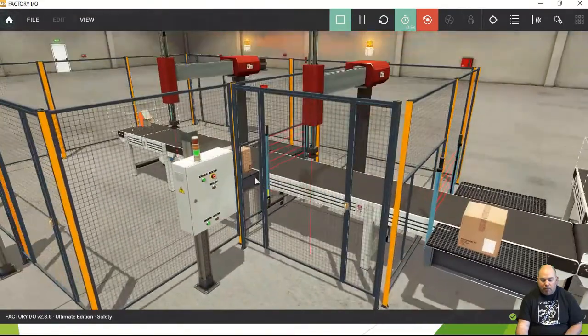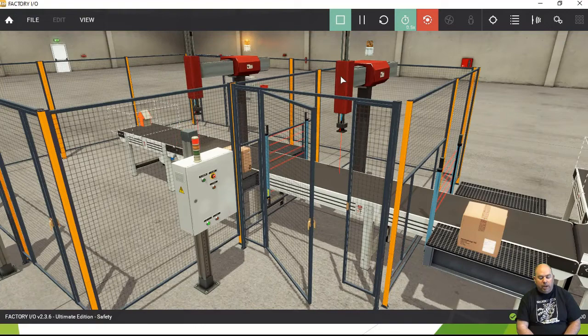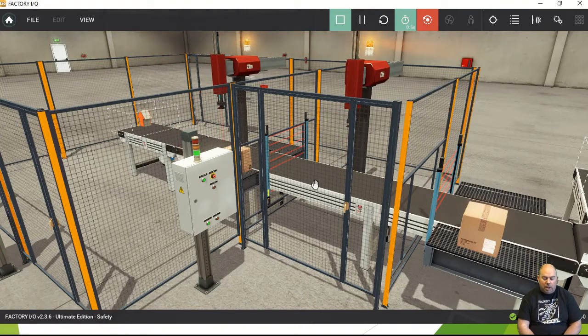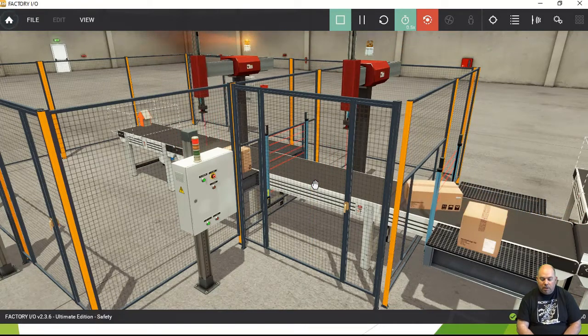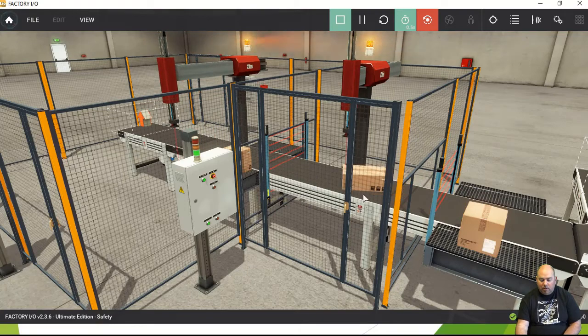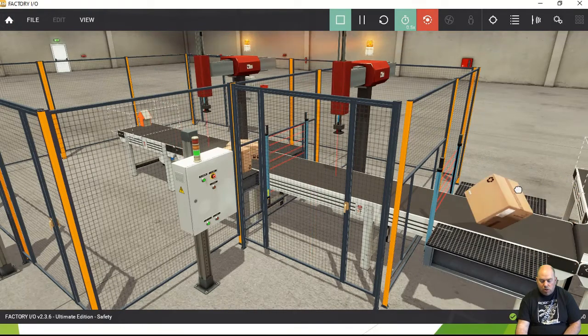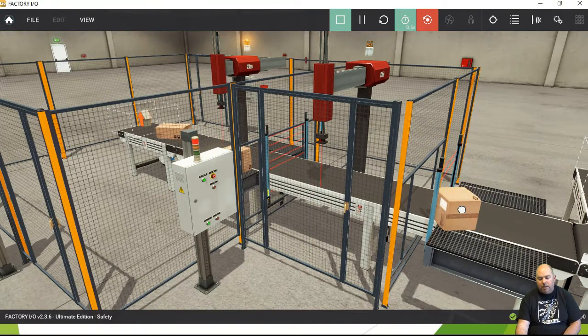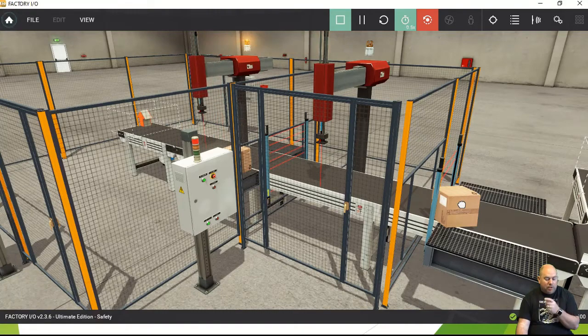In the simulation: if we open this gate, gantry one stops because that breaks the perimeter of zone one. We close the gate, reset, and we're running again. Now watch when a box comes along and the light curtain gets broken — that stops gantry one. If a box is breaking that light curtain, zone one is broken because this light curtain makes up part of the perimeter for zone one.